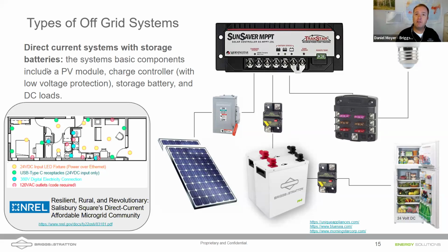We've got a solar panel—if you're living off-grid you probably don't have that disconnect, but you might. I'm feeding it into that Morningstar SunSaver, chosen because it has a built-in low battery voltage disconnect. We feed in solar and feed in our battery; you probably don't need this little breaker here since our batteries have breakers built in, but I added it anyway in case there are code inspectors on the call. Then we take the DC out of the low voltage battery disconnect, feed it into that Blue Sea Systems power distribution block with the fuses, and then feed it up to our loads.